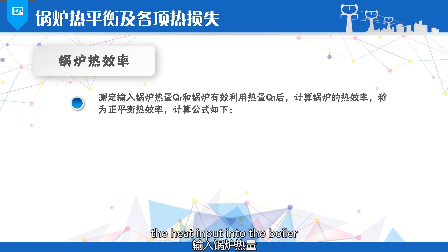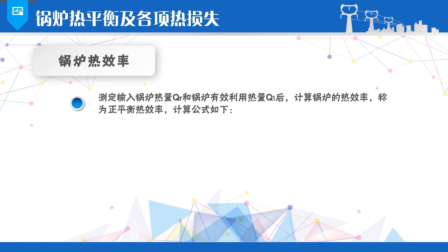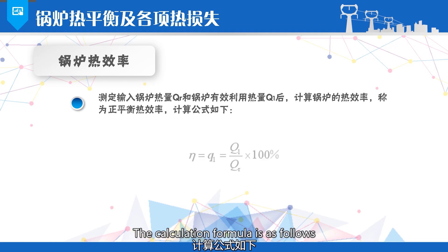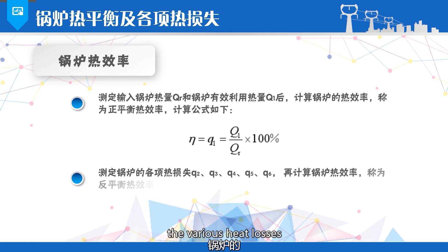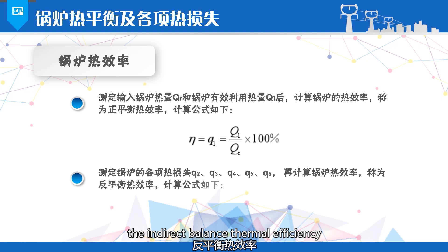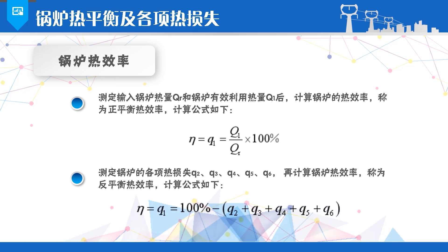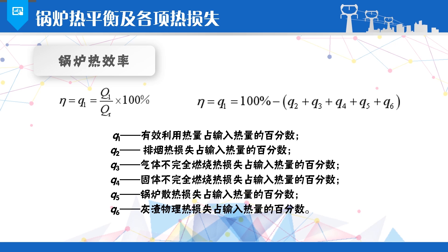Boiler thermal efficiency can be determined through two methods. The first method is to measure the heat input into the boiler and the effective heat utilization, and then calculate the boiler's thermal efficiency — this is referred to as the direct balance thermal efficiency. The calculation formula is: η = Q1 / Qr × 100%. The other method is to measure the various heat losses of the boiler and then calculate the boiler's thermal efficiency — this is referred to as the indirect balance thermal efficiency. The calculation formula is: η = 100% − (Q2 + Q3 + Q4 + Q5 + Q6).